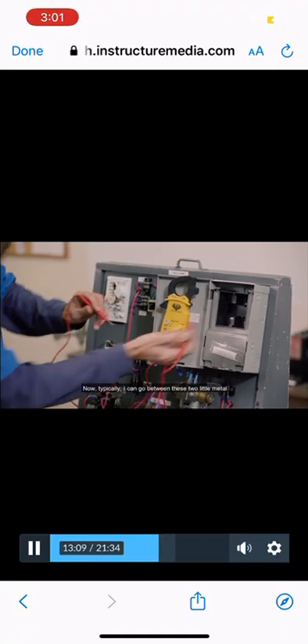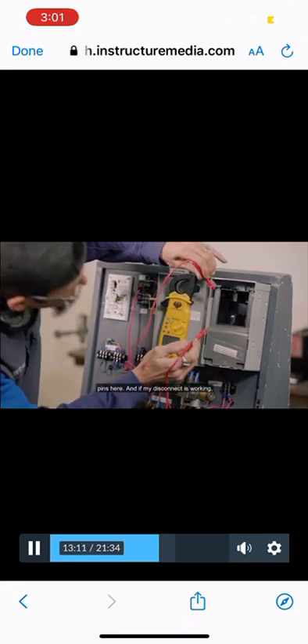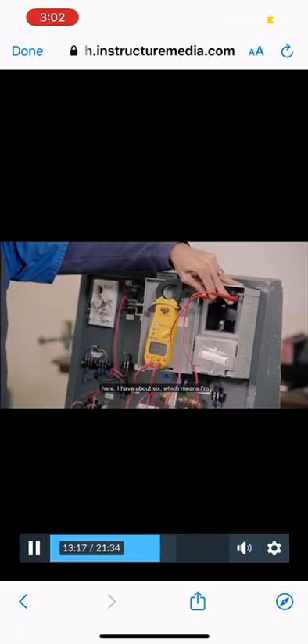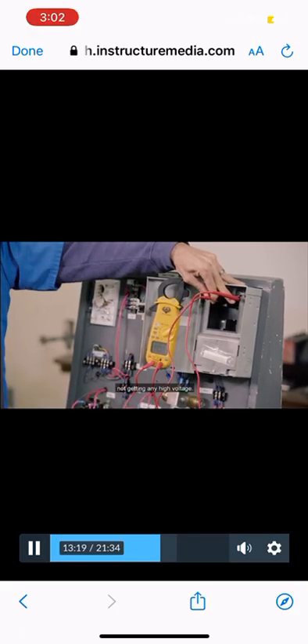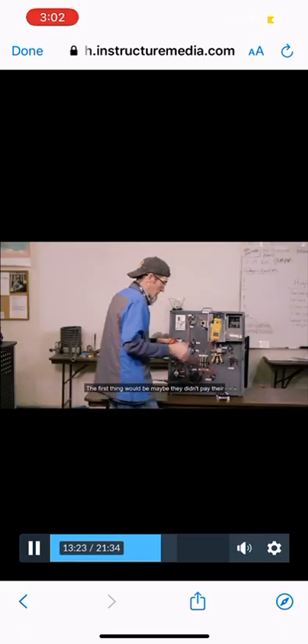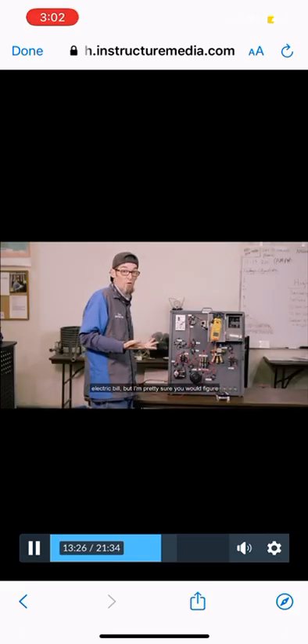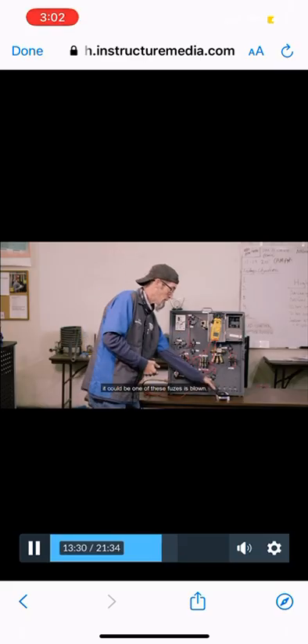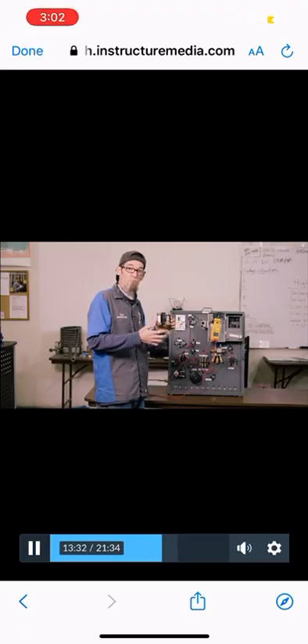And there's little metal pins in here. Now typically I can go between these two little metal pins here, and if my disconnect is working, I should have 120 volts coming in here. I have about 6, which means I'm not getting any high voltage. So there's two things that are going to cause that. The first thing would be maybe they didn't pay their electric bill, but I'm pretty sure you would figure that out because nothing in their house would be on. Or it could be one of these fuses is blown.